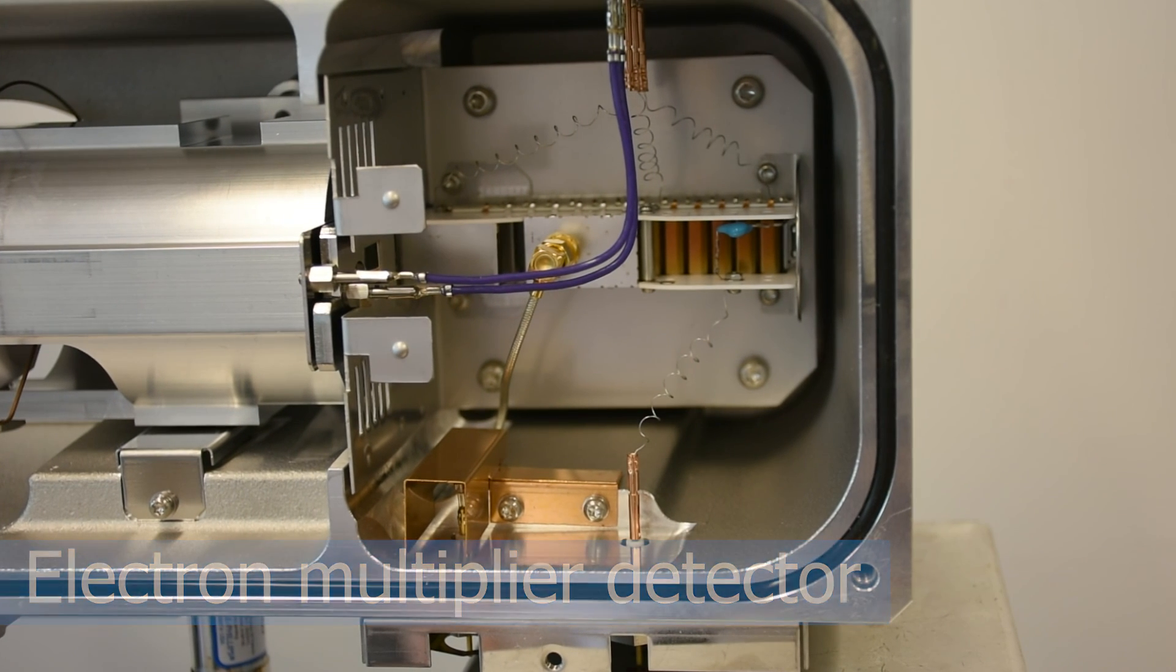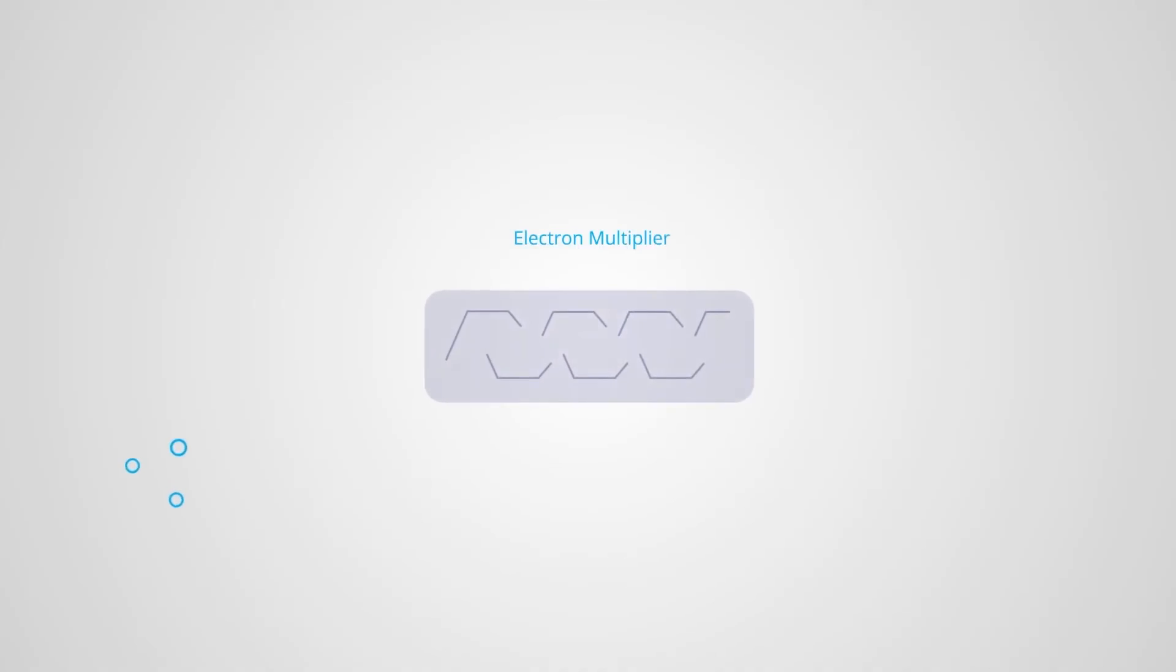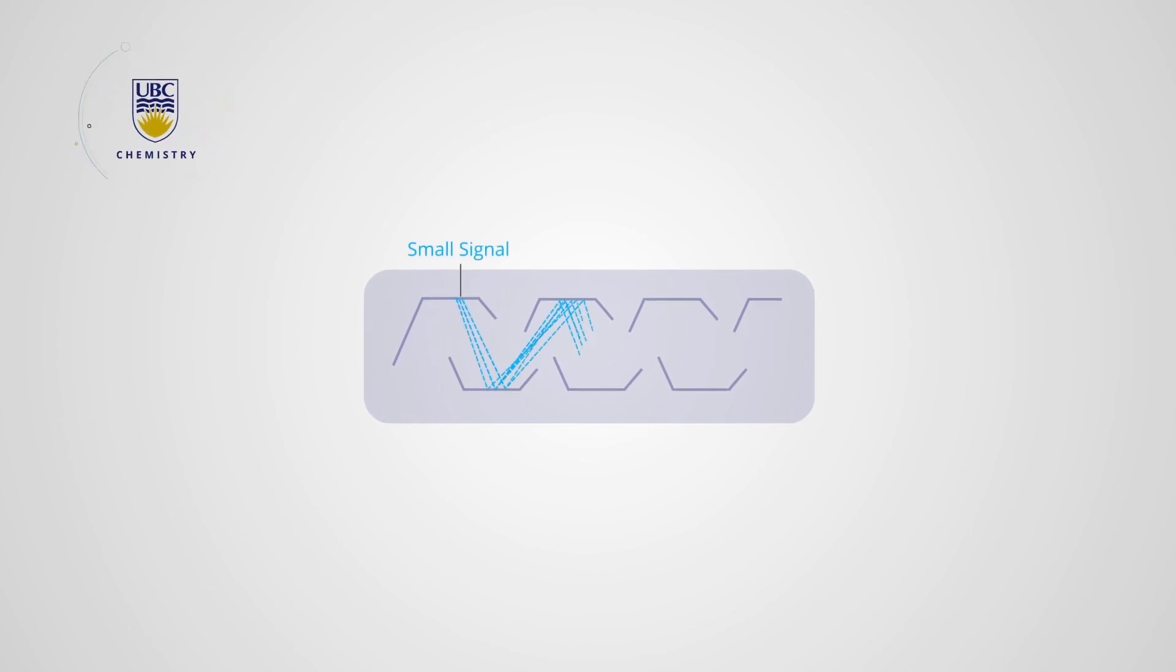The detector is an electron multiplier. Ions entering it strike a cathode, which causes multiple electrons to be emitted. These are accelerated into another electrode, ejecting even more electrons. This process repeats several times until the now large flow of electrons reaches the anode, where the current is measured. The signal is converted to digital form, which goes to the computer.